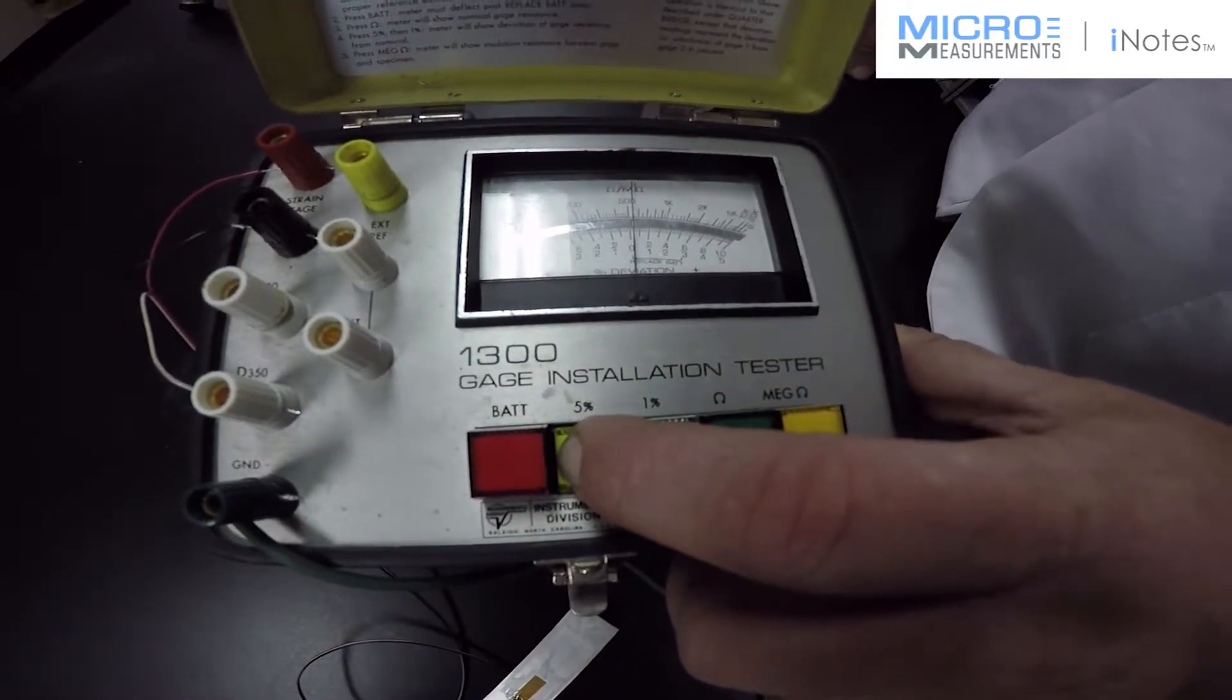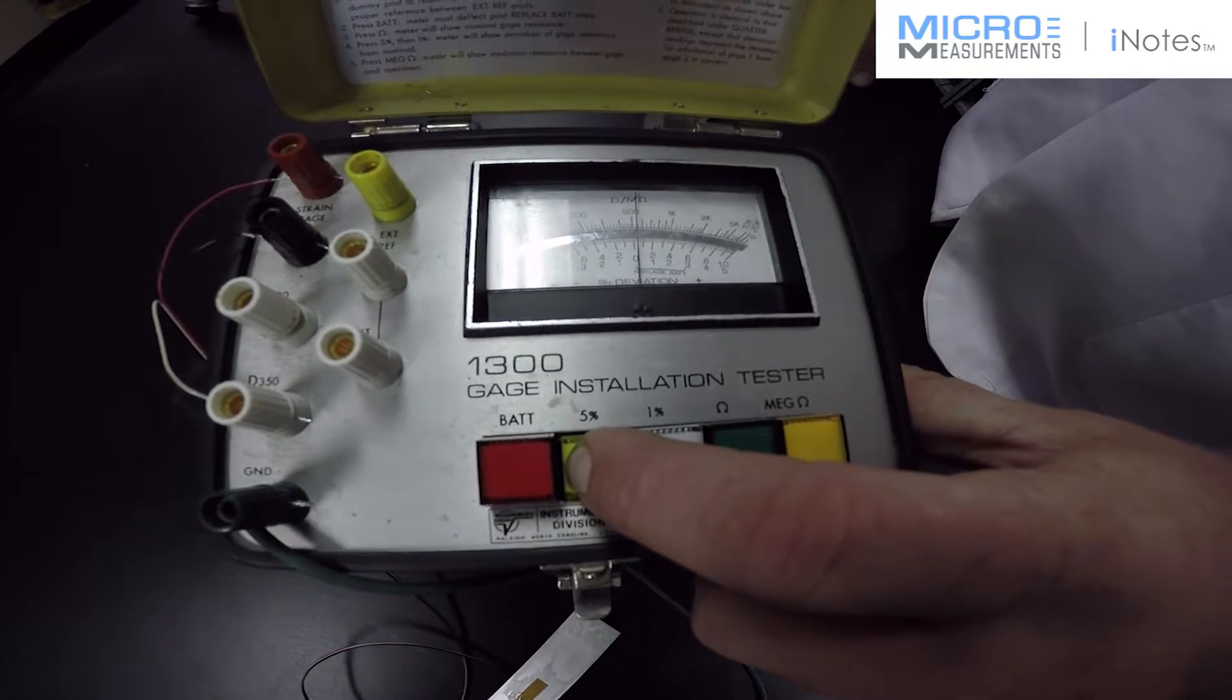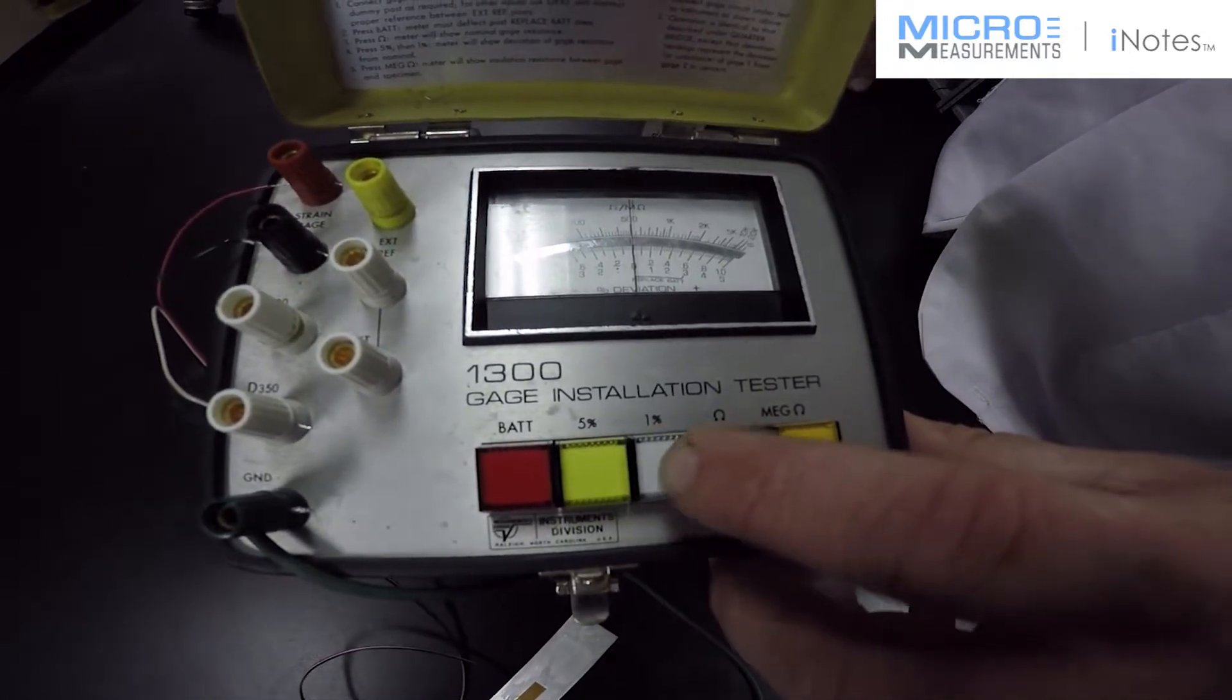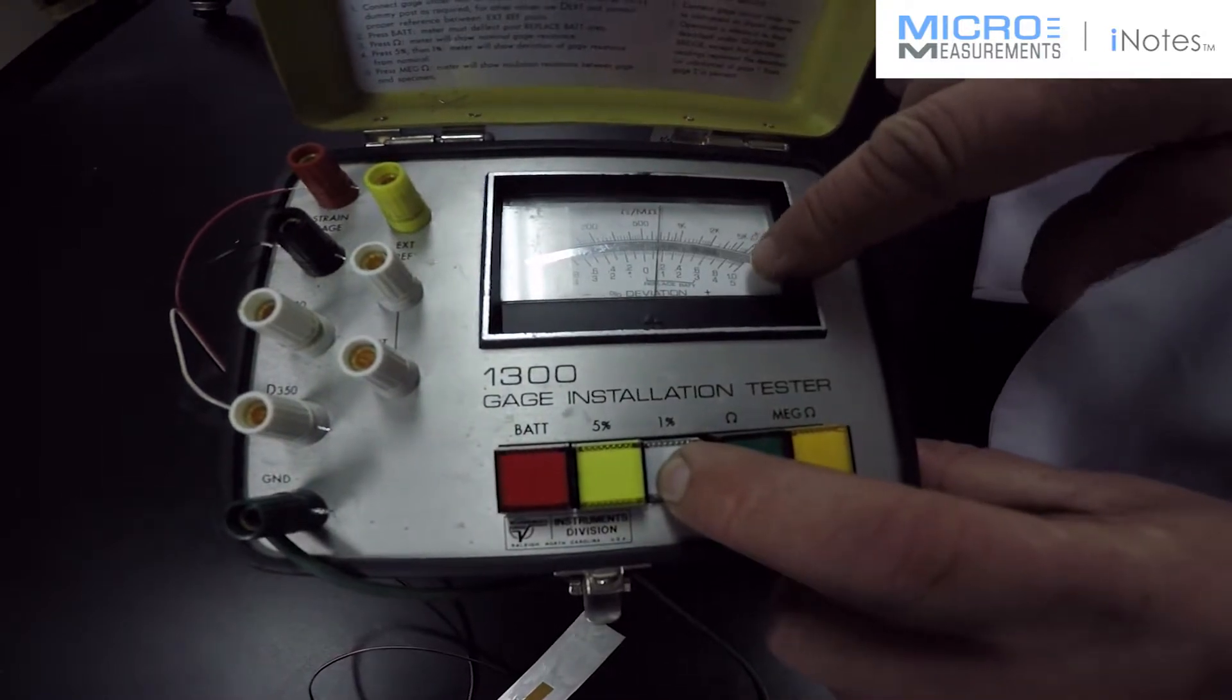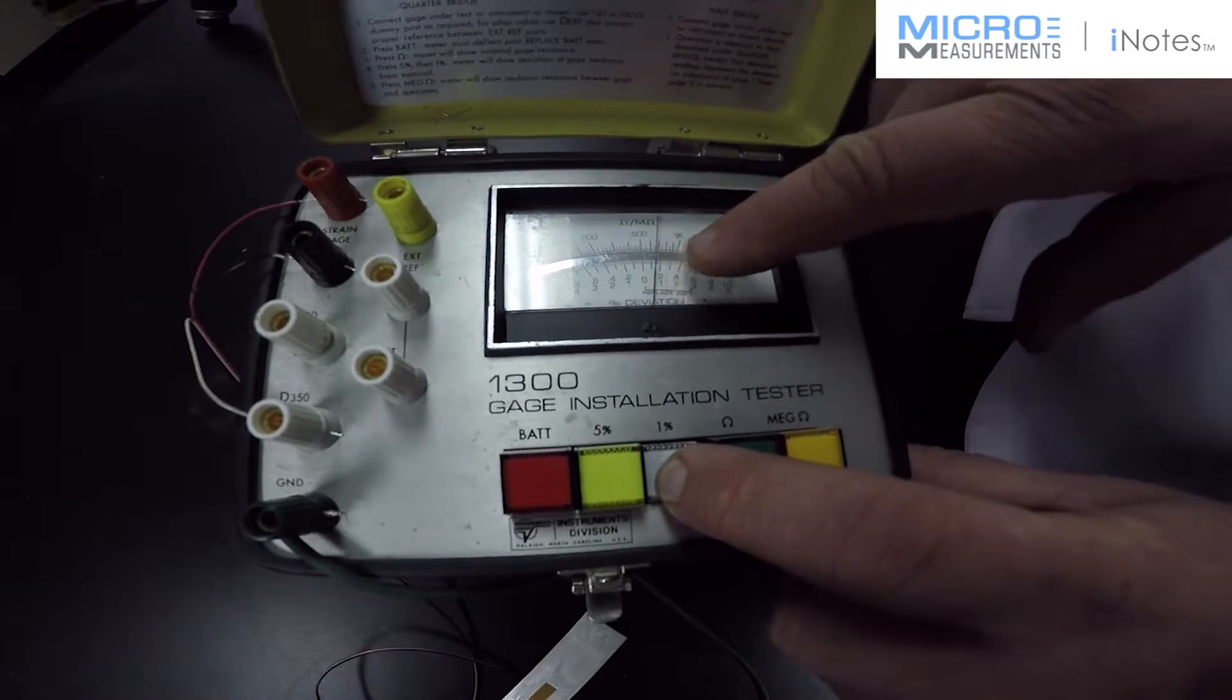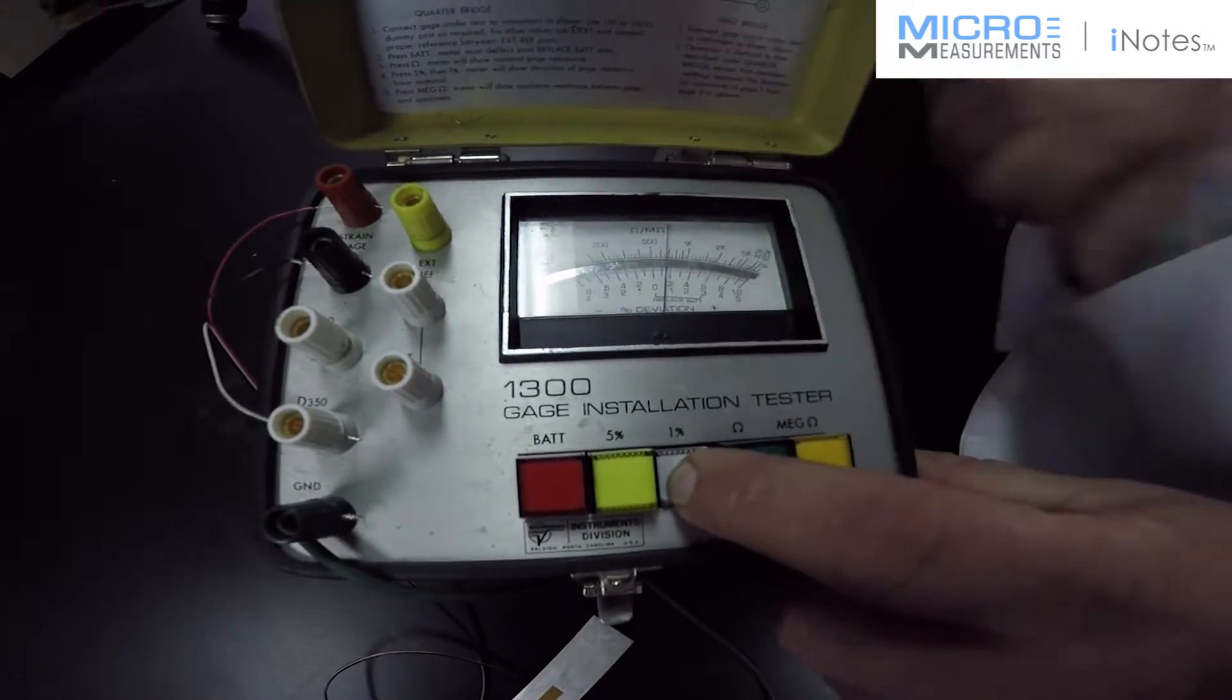So if I press the 5% button, you can see that the needle barely moves. So I need to zoom in on it a little bit, get a closer reading. So I'll push the 1% button. Now I'm reading on the 1% scale, plus or minus. And I can see that I'm about 0.15% of 350 ohms.